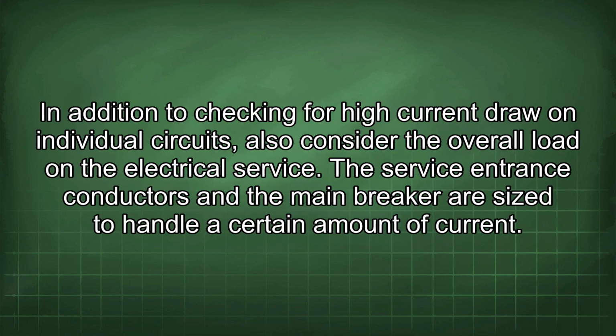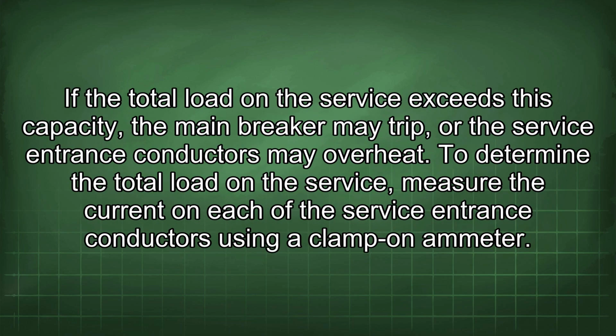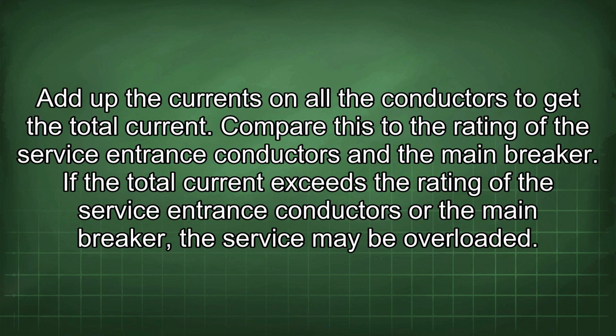In addition to checking for high current draw on individual circuits, also consider the overall load on the electrical service. The service entrance conductors and the main breaker are sized to handle a certain amount of current. If the total load on the service exceeds this capacity, the main breaker may trip, or the service entrance conductors may overheat. To determine the total load on the service, measure the current on each of the service entrance conductors using a clamp-on ammeter. Add up the currents on all the conductors to get the total current. Compare this to the rating of the service entrance conductors and the main breaker.